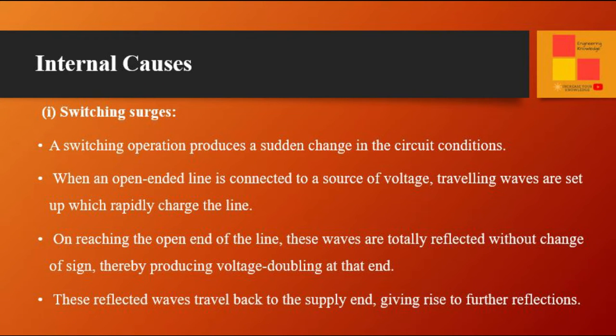Switching surges is defined as: a switching operation produces a sudden change in the circuit conditions. When an open-ended line is connected to a source of voltage, traveling waves are set up which rapidly charge the line. On reaching the open end of the line, these waves are totally reflected without change of sign, thereby producing voltage doubling at that end. These reflected waves travel back to the supply, giving rise to further reflections.